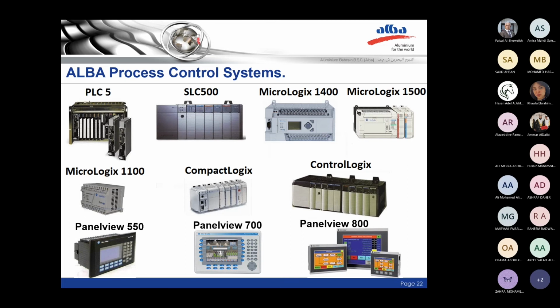Then, finally, we reach the PanelView in level 1. The purpose of PanelView is to be front-end software for the operator. Normally, the operator does not have the capability to access the PLC software. The PLC software is controlling some machine, and the operator will be responsible for that machine. In case he needs to run that machine, or make some arrangement to that device, machine, or equipment, he cannot access the PLC. So the interface between the operator and the machines through the PLC is the PanelView.